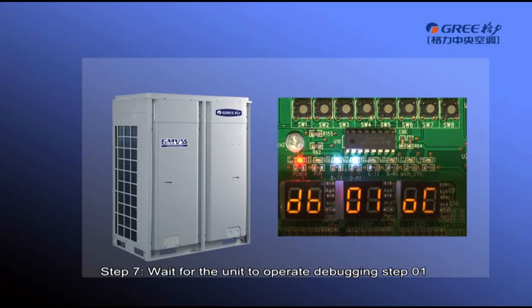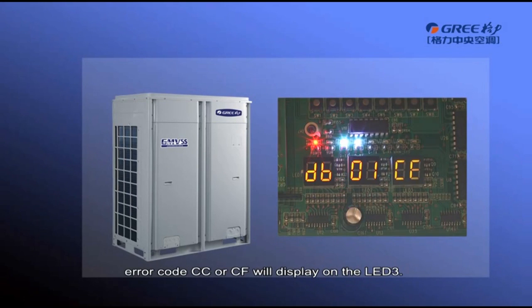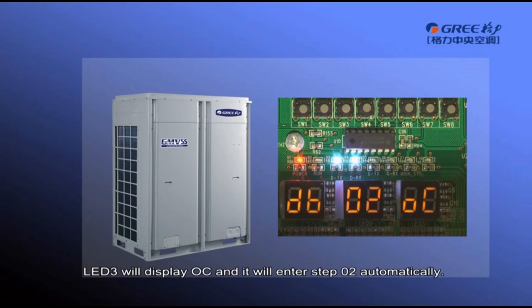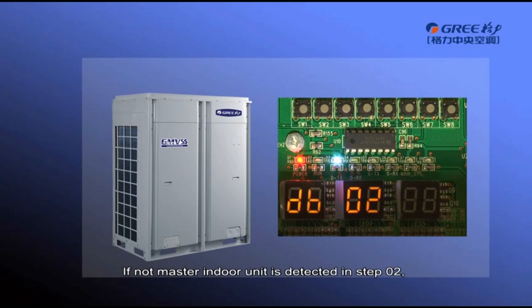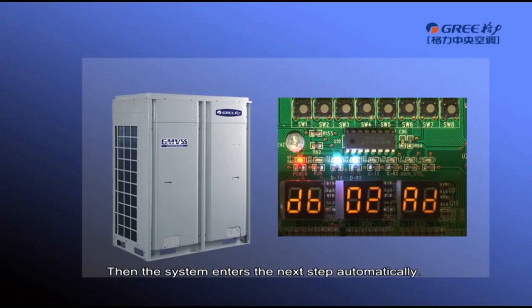Wait for the unit to operate debugging Step 01 and Step 02 automatically. If the master module is incorrect, error code CC or CF will display on LED3. CC means the system does not have a master module set; CF means the system has more than one master module. When a master module is set successfully, LED3 will display OC and it will enter Step 02 automatically. If no master indoor unit is detected in Step 02, LED3 will display error code L7 and all outdoor unit buttons are temporarily not functioning. Users can set the master indoor unit through the debugging software, wired controller, or remote controller within one minute. If no master indoor unit is set within one minute, the system will set one automatically, then enters the next step.